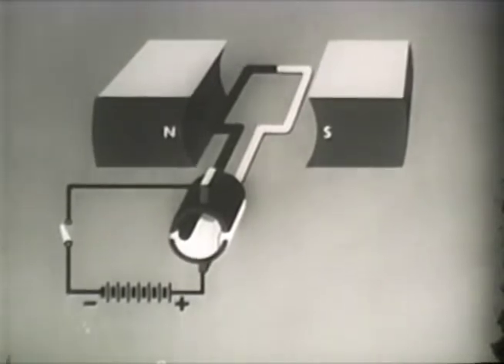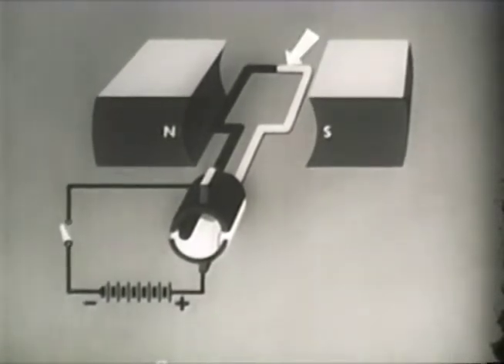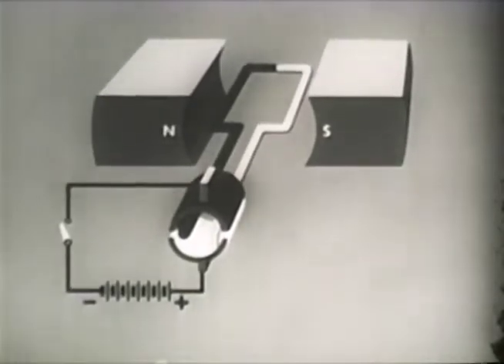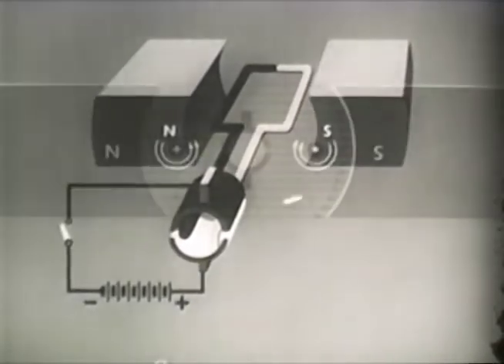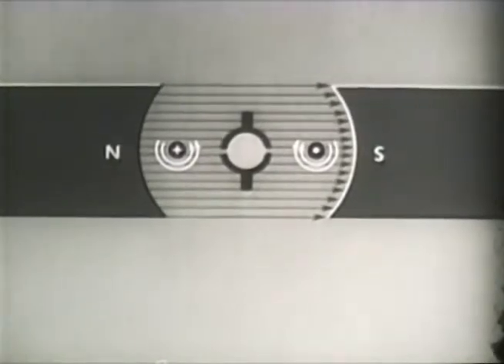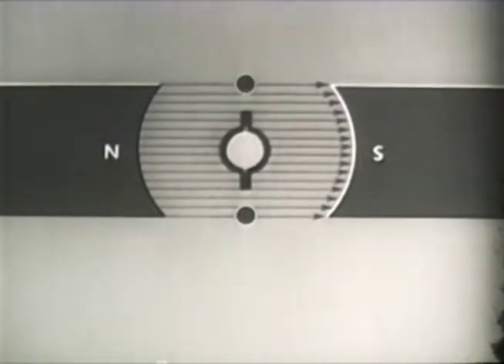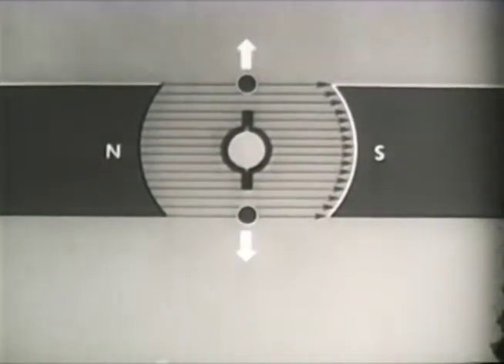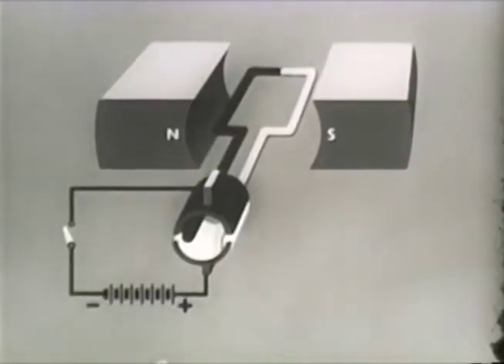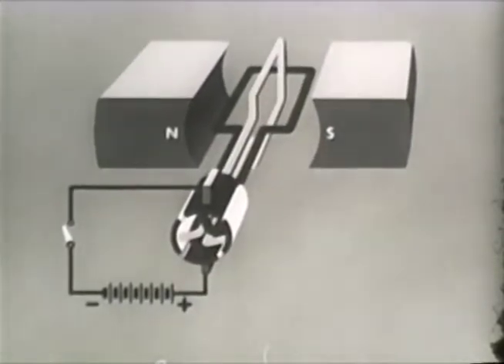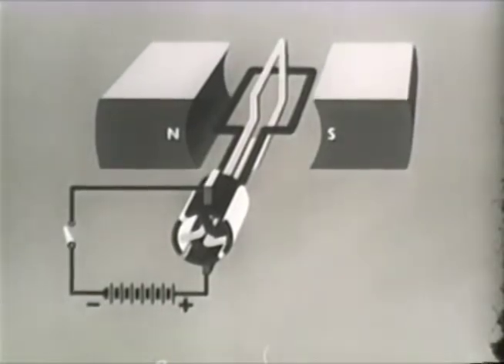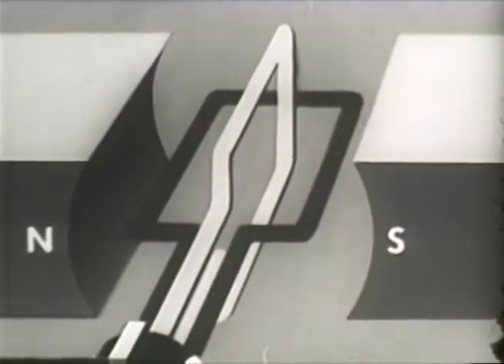The basic DC motor, like the DC generator, consists of a pair of magnetic poles, an armature made up of a single turn loop, a commutator, and a brush assembly. A conductor in a magnetic field will move when a voltage is applied to it. With the voltage applied and the magnetic field and current flow as shown, the right conductor will be pushed down while the left one is pushed up. Since the forces on each conductor are now in exact balance, there will be no more motion. Adding another loop and two commutator segments ensures that at no time will balancing forces cancel each other out. With this setup, there will be motion at all times.